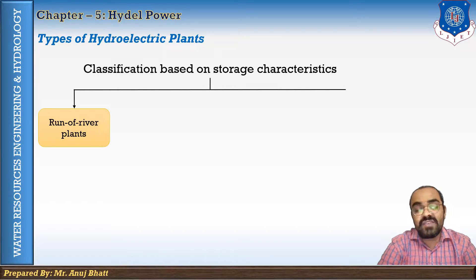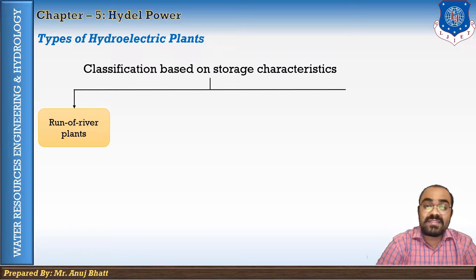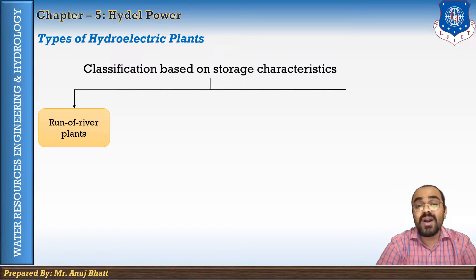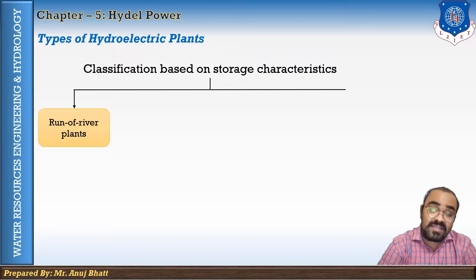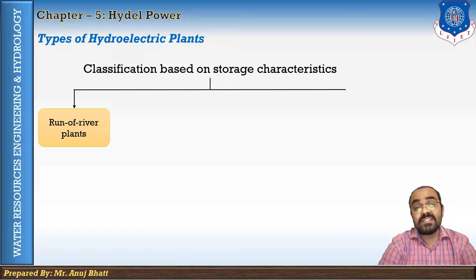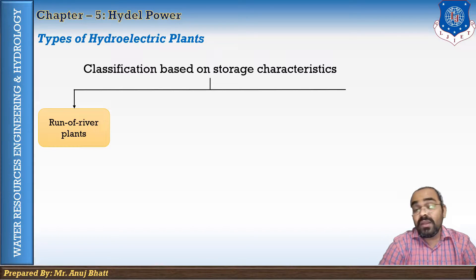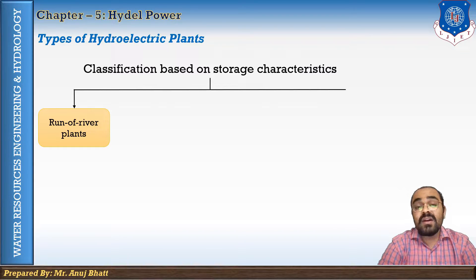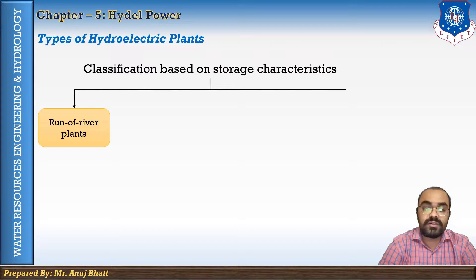Such a scheme is essentially a low-head scheme and is adopted in the case of a perennial river which has a minimum dry weather flow of such magnitude that makes development worthwhile. In such plants, sometimes the tailwater rises to a high level during floods, making plants inoperative. In some cases, small storage or pondage is provided for tiding over hourly fluctuation of load. When available flow exceeds demand, excess water can be stored temporarily in the pond upstream.